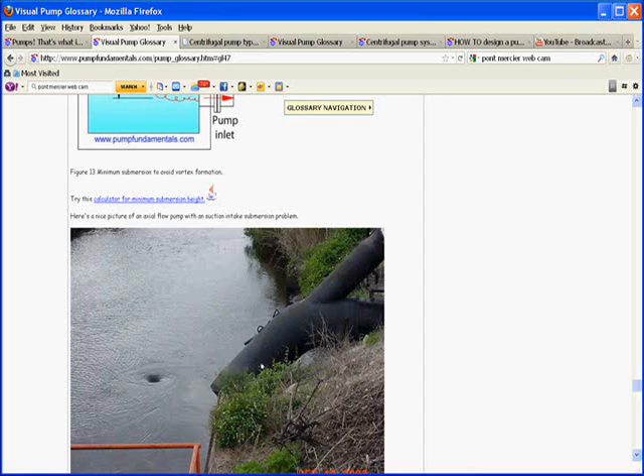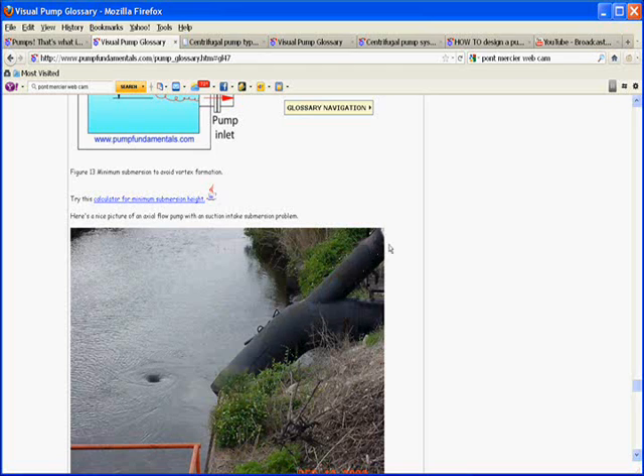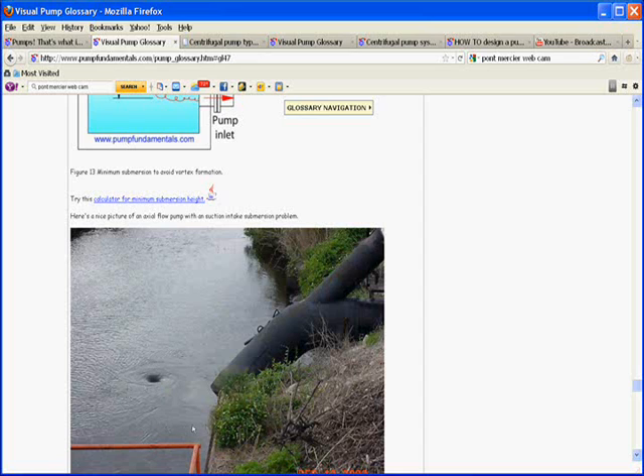The pump is actually going into the water here, and the propeller and our vanes are probably located around here. This is the discharge, and this is the drive shaft. You can see here, the level in the water of the creek is a bit low, so we're getting this vortex formation. So they'll be getting air into the pump and reducing their capacity.